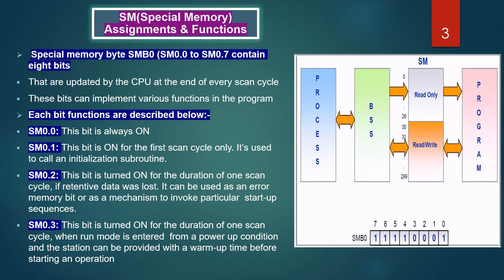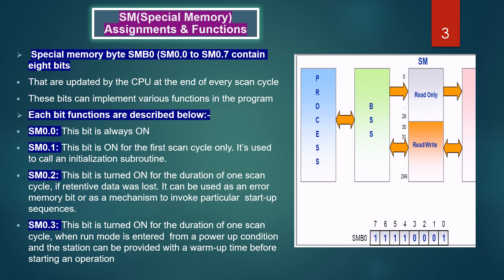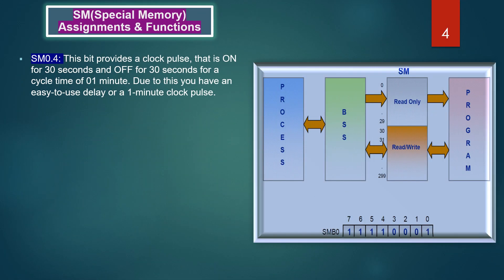SM 0.3: this bit is turned on for the duration of one scan cycle when run mode is entered from a power-up condition. That way, the station can be provided with a warm-up time before starting an operation. SM 0.4: this bit provides a clock pulse that is on for 30 seconds and off for 30 seconds, for a cycle time of one minute, giving you an easy-to-use delay or a one-minute clock pulse.